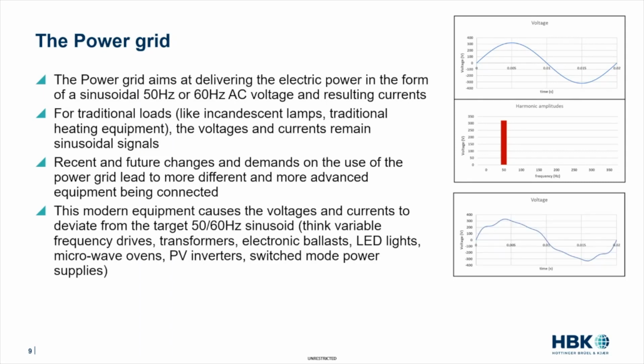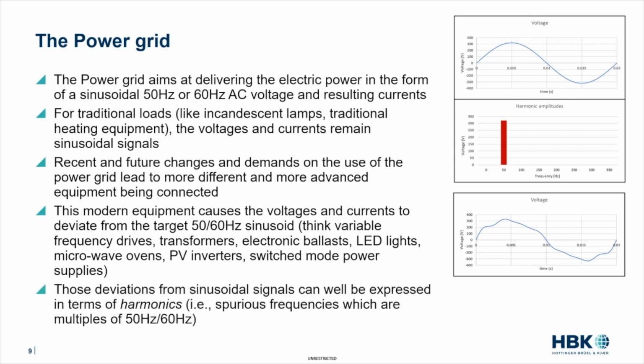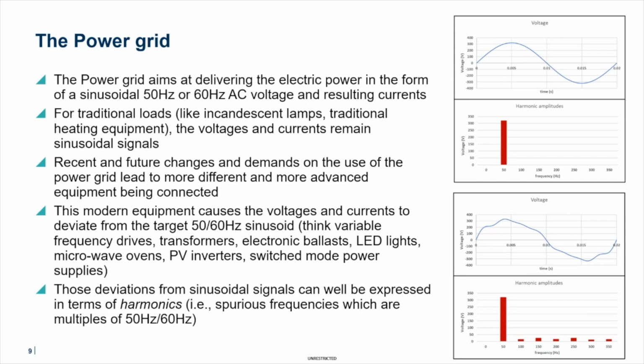So what you will get, for example, if you put a nonlinear or switching load on your power grid, is a voltage or a current that still looks a bit like a sine wave, but is not really a sine wave. There is a deviation in your voltage and current signals from the ideal sine wave. And this deviation from a perfect sine wave can very well be expressed in terms of harmonics. If you look at this kind of time signal in the frequency domain, it looks something like this.